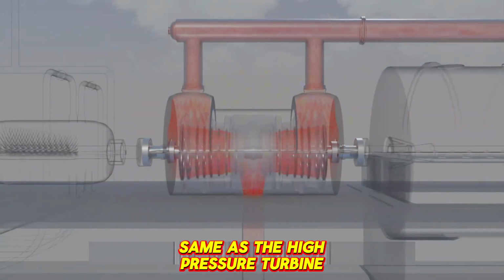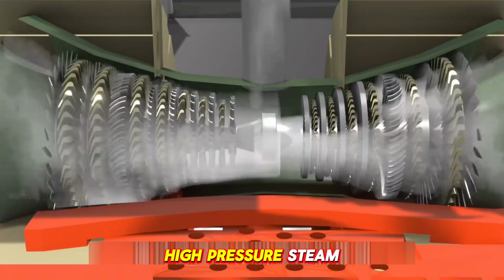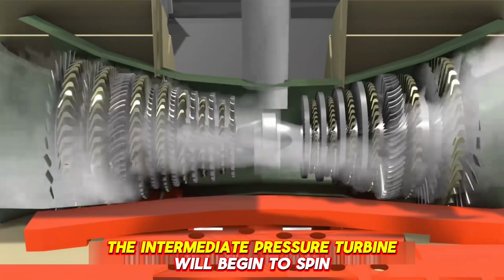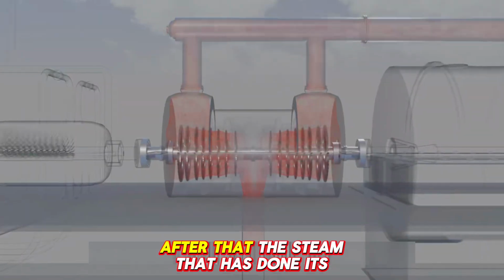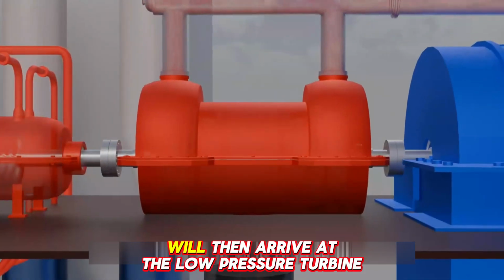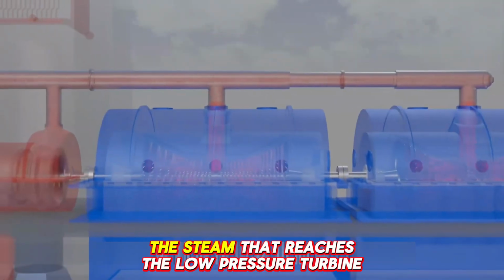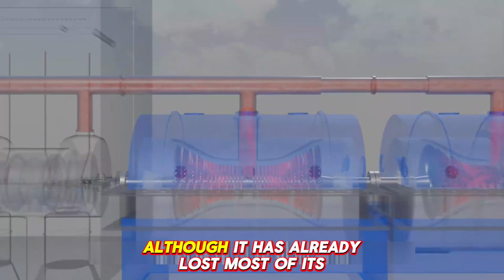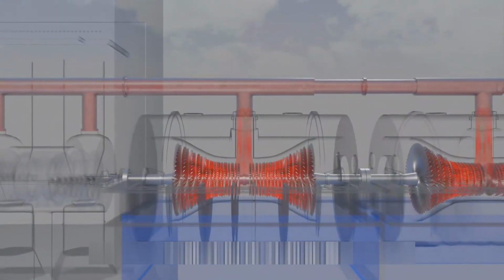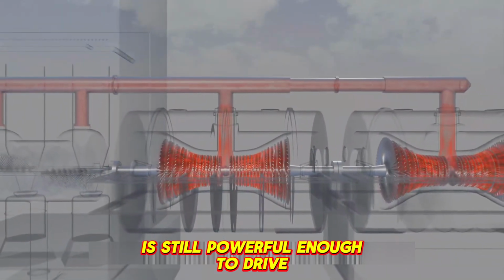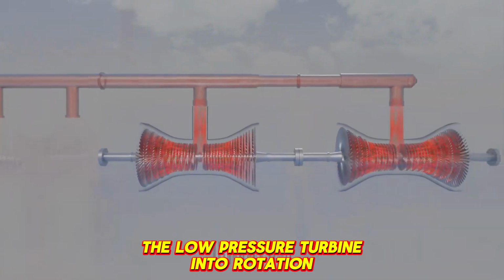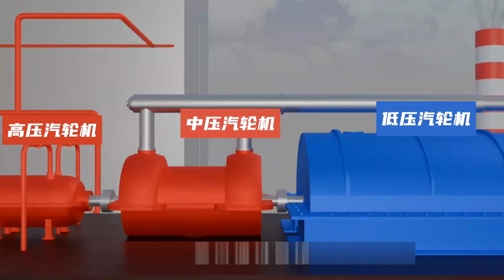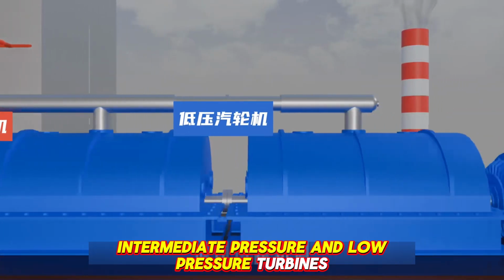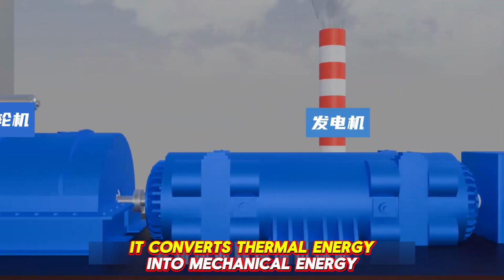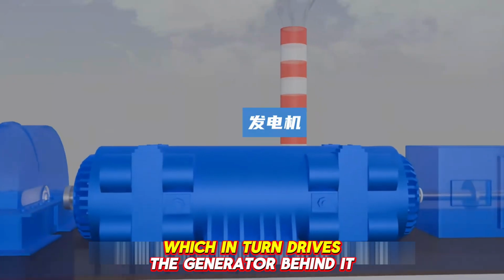Same as the high-pressure turbine, propelled by the high-temperature, high-pressure steam, the intermediate pressure turbine will begin to spin at high speed. After that, the steam that has done its work will then arrive at the low-pressure turbine. The steam that reaches the low-pressure turbine, although it has already lost most of its pressure and energy, is still powerful enough to drive the low-pressure turbine into rotation. As the steam passes through the high-pressure, intermediate pressure, and low-pressure turbines, it converts thermal energy into mechanical energy, which in turn drives the generator behind it to produce electricity.